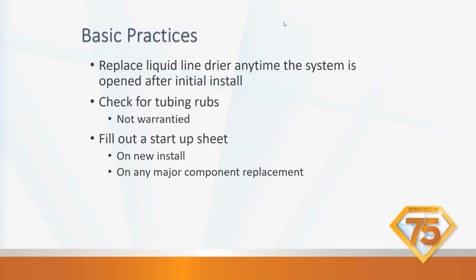You should be checking all that stuff again every time you go out there, because the unit is going to vibrate. It's a mechanical piece of equipment. It vibrates. It's going to make a little bit of noise. So just remember that as you're doing all your stuff. Fill out a startup sheet on new install and on any major component replacement, okay?